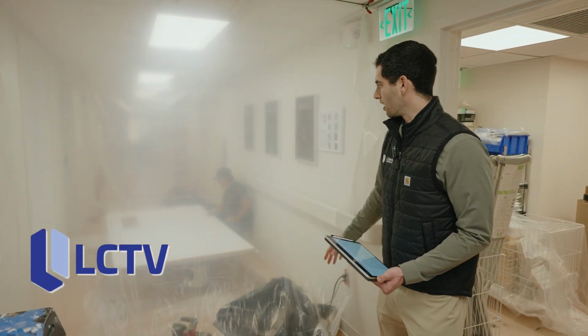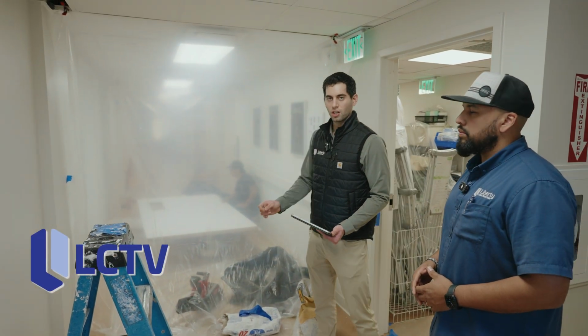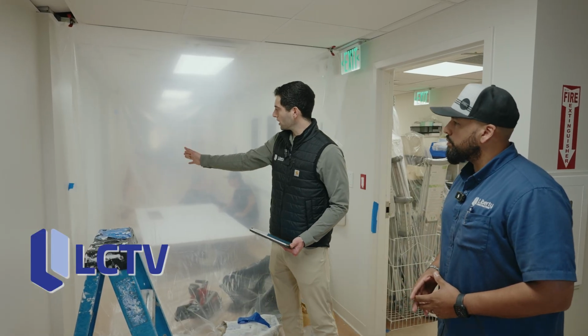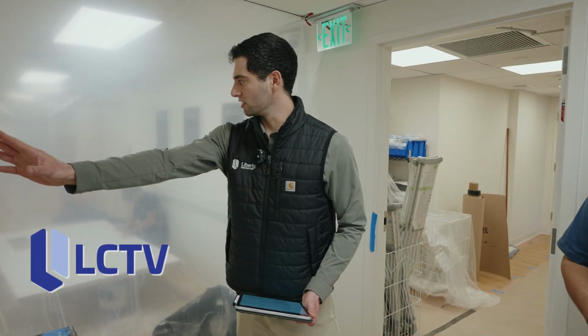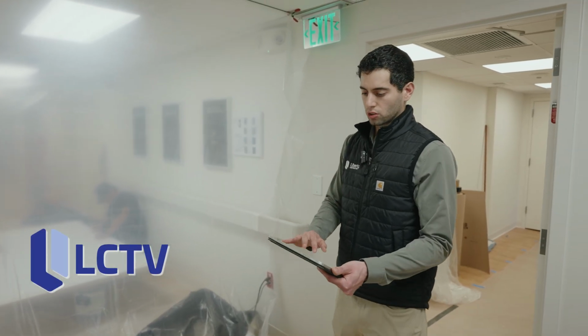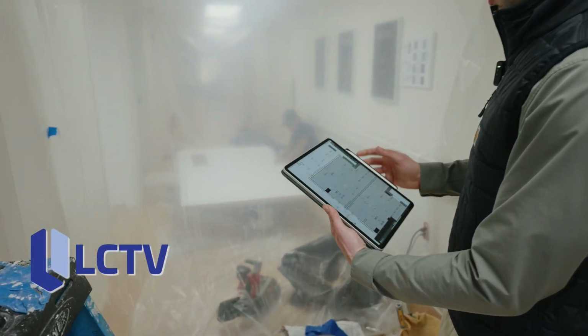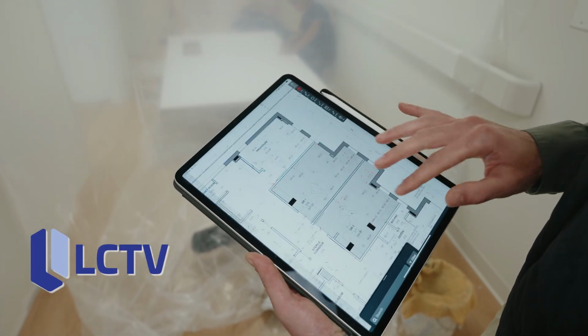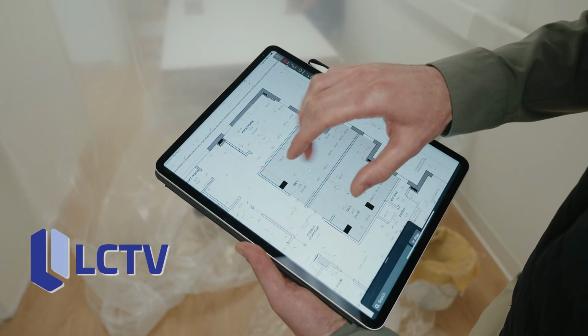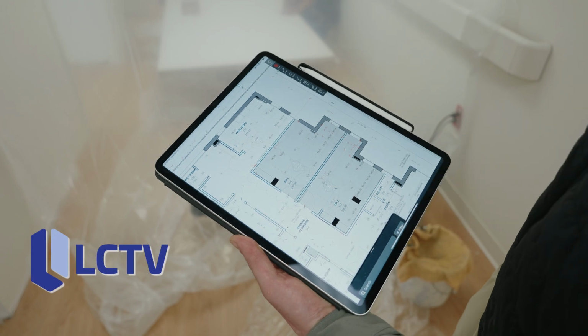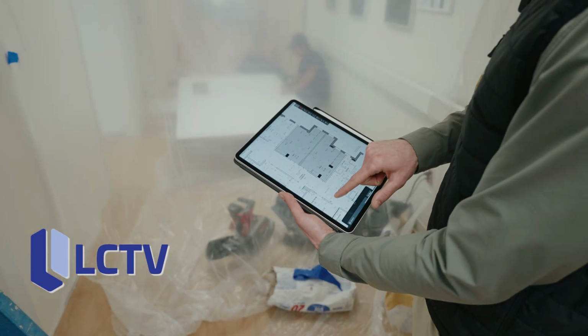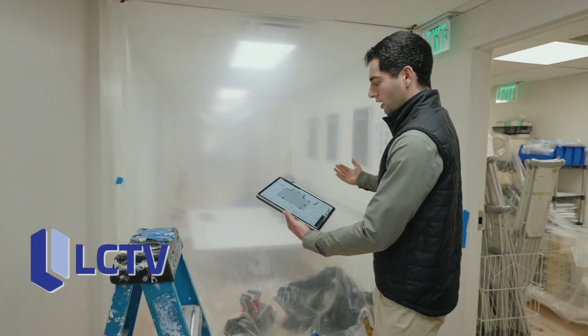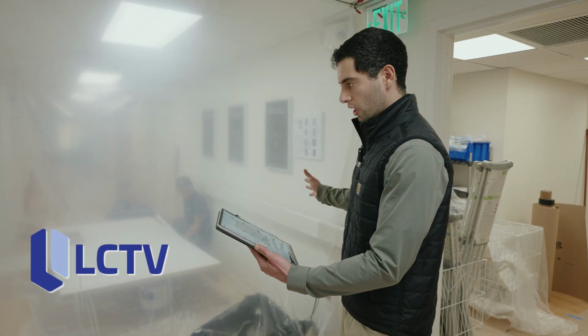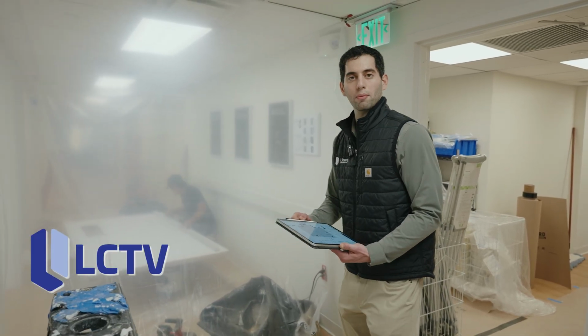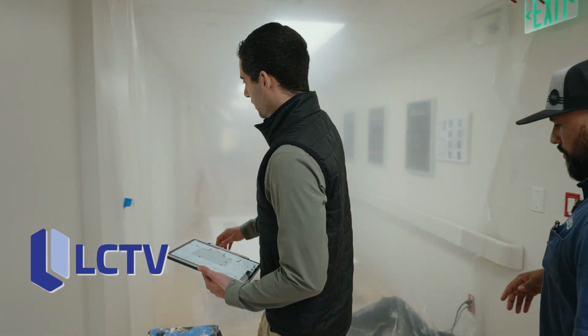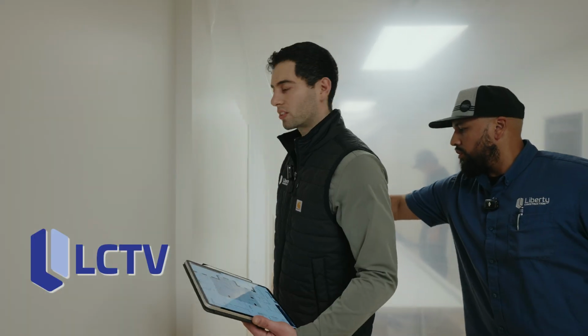You can see we tarped off where the 2 operating rooms are. These are the 2 rooms that originally were 240 usable square feet. We've already pushed out the walls to line up with this existing wall, making them over 270 - in the new design, 287 square feet. These are the new walls we put in. This shrunk the hallway to 7 feet wide, which is still okay since it's not smaller than the clearance needed for a gurney, which wouldn't fit through a 3-foot wide door anyway. So a 7-foot hallway is still good. And most importantly, we now have well more than the 270 minimum required usable square feet - close to 290 now. So even if they don't count the space for the anesthesia cart, we'll still be good.